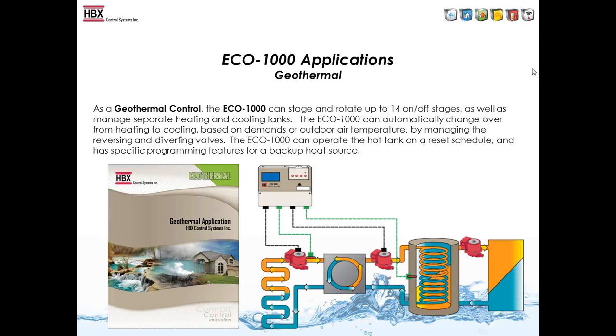In the Geo Application, we can do up to 14 stages of on-off or 7 2-stage compressors. This can also be used for chillers also, as it doesn't necessarily have to be using heat pumps. In this illustration, we are using a single tank and then out to the load. So the ECO-1000 controls everything from the tank to the left. If you want to put the Zone 500 on, you can control the zones out from the tank. So basically this is a single tank with a single heat pump and then out to the ground loop. It can also control a backup heat source.